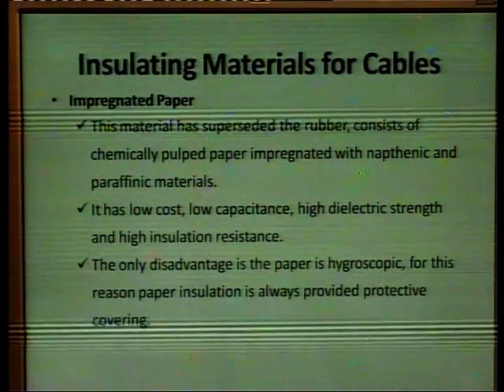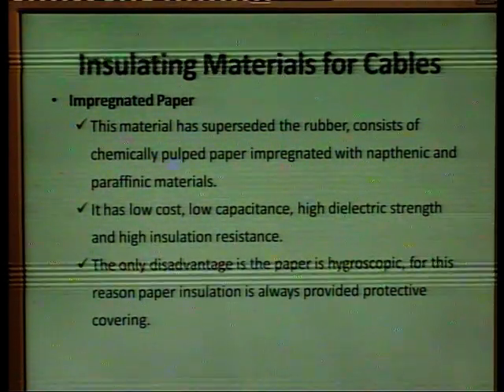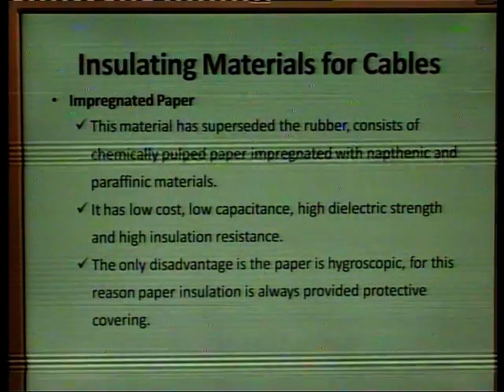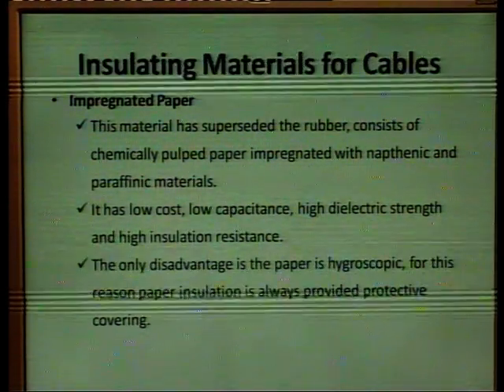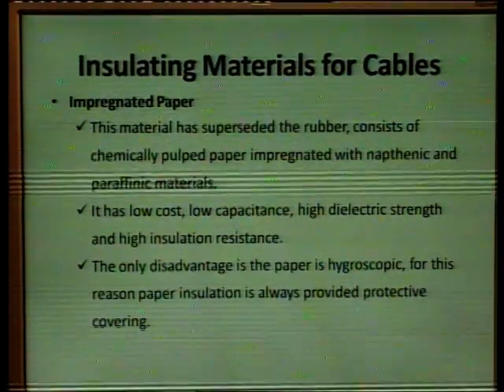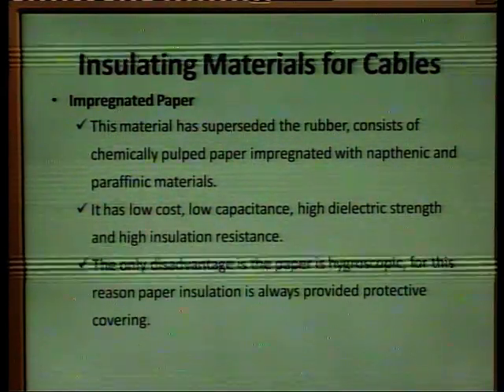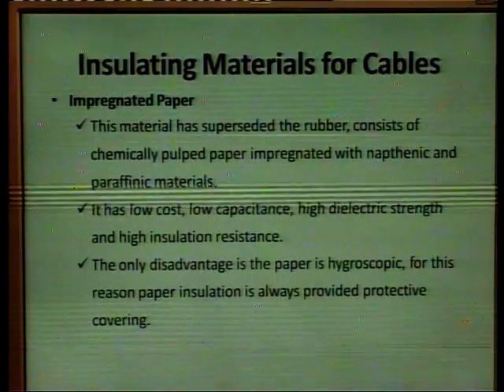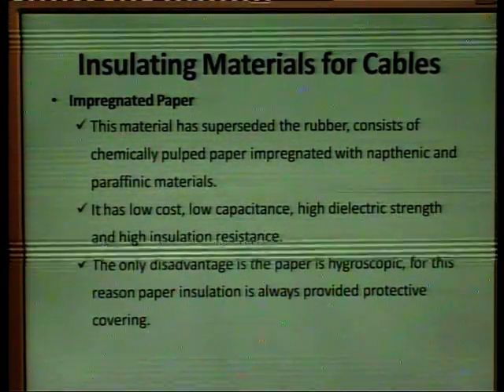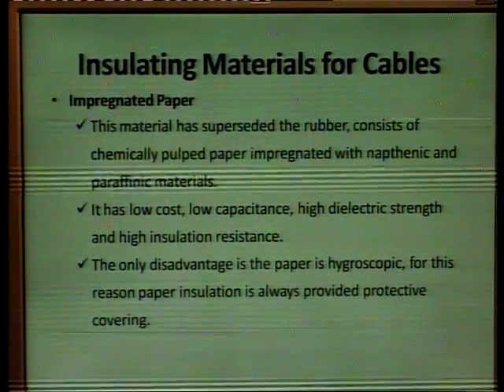Then the next insulating material is the impregnated paper. This material has superseded the rubber. It consists of chemically pulped paper, which is impregnated with naphthenic and paraffinic materials. Then it has low cost, low capacitance, high dielectric strength and high insulation resistance. And the only disadvantage is that the paper is hygroscopic. For this reason, paper insulation is always provided with a protective covering.